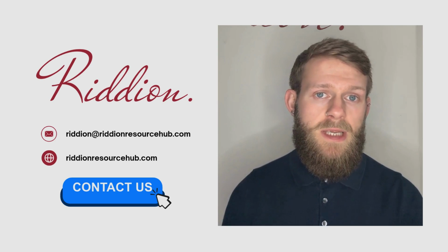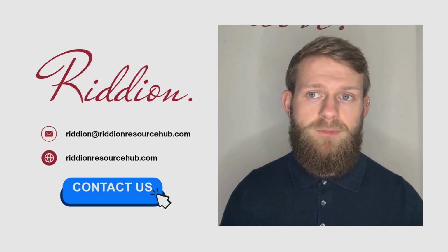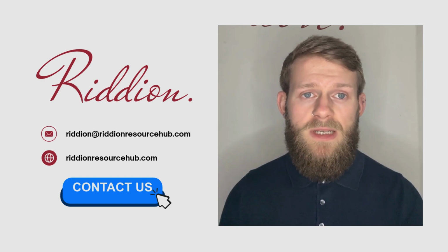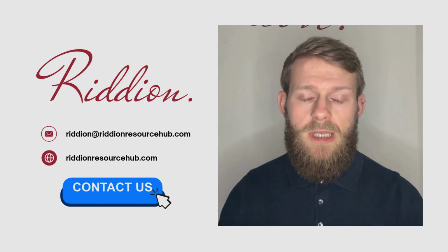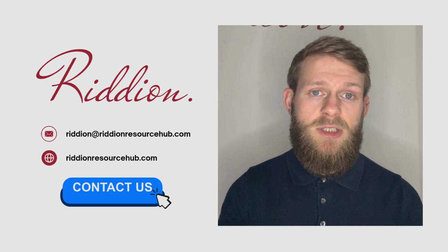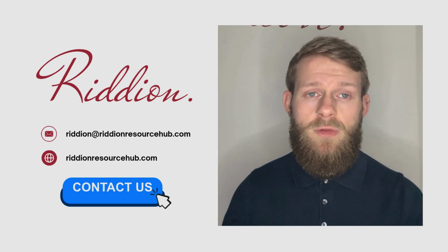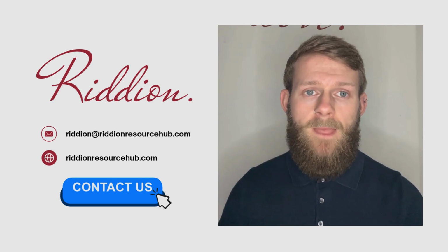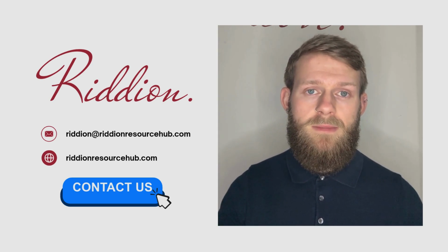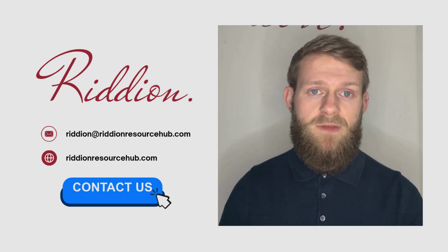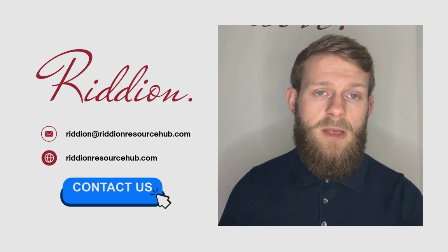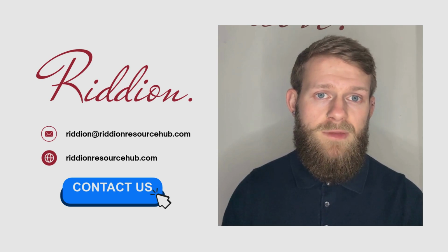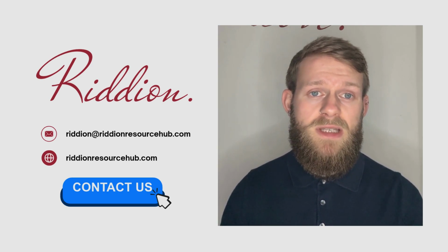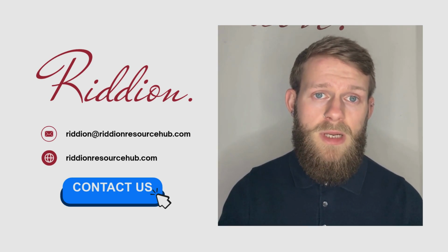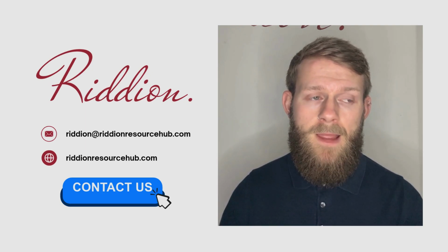So what happens in a 13485 audit? The audit is conducted by a certification body, which is an external organisation that assesses whether your QMS meets ISO 13485 standards. Passing this audit isn't all just about getting a certificate to hang on the wall. In many markets, ISO 13485 certification is essential for demonstrating compliance before placing your medical devices on the market.